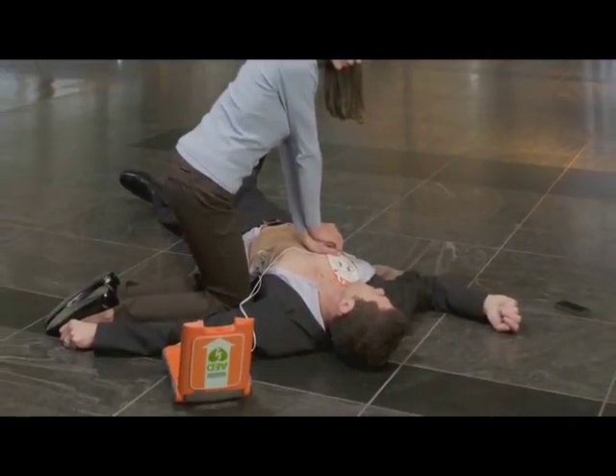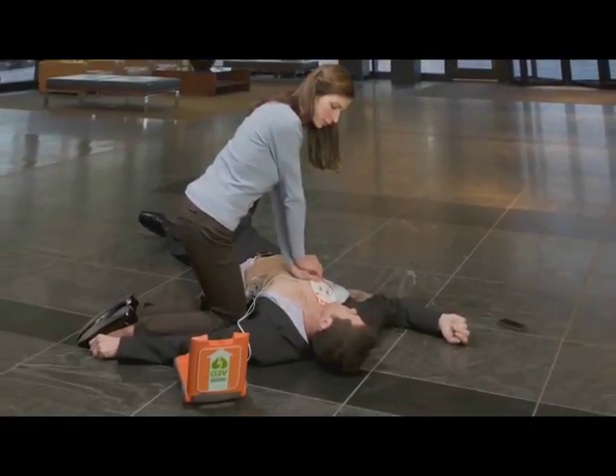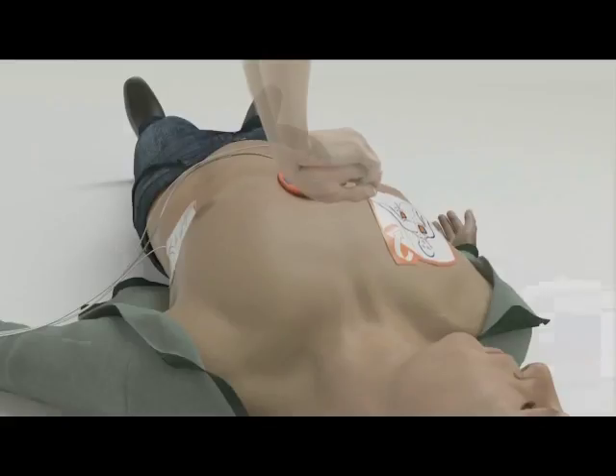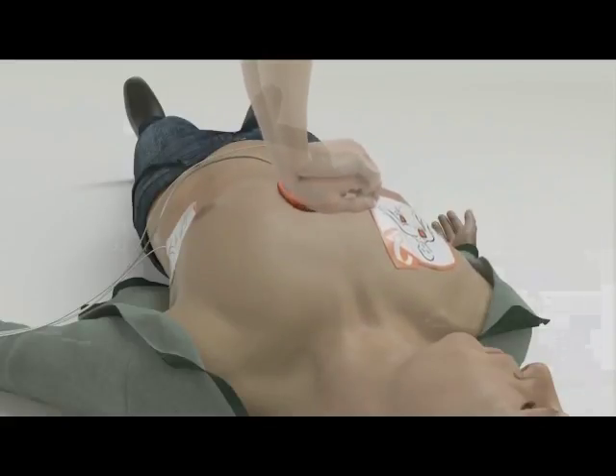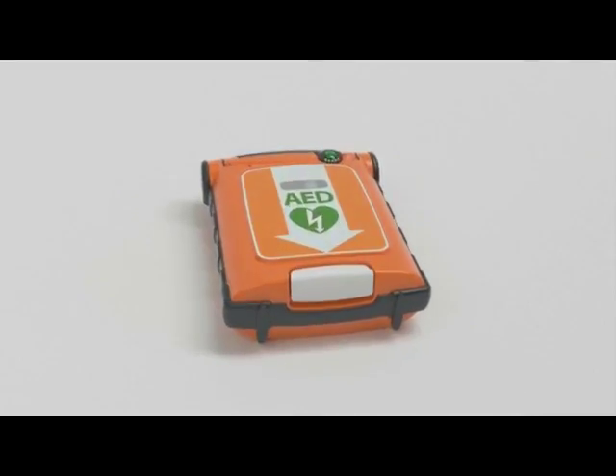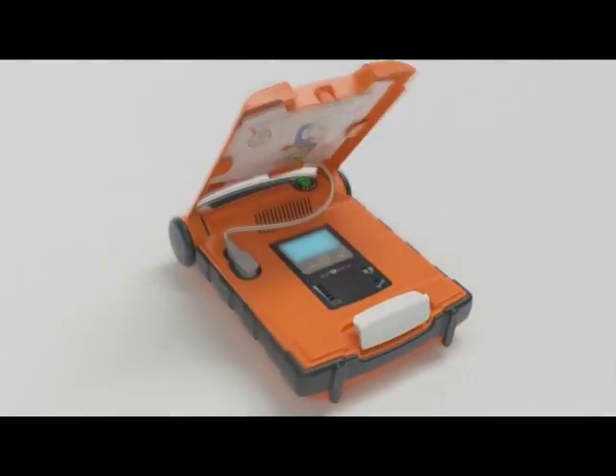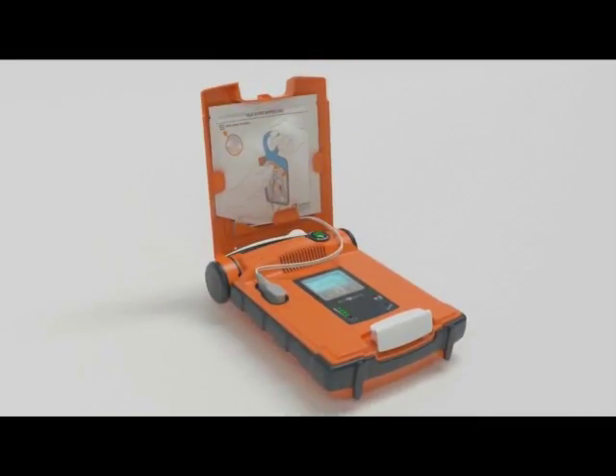The G5 will give you feedback on how effectively you are performing CPR. The G5 will advise if you are doing your compressions correctly — either too fast or too slow, too deep or not deep enough. If there is no green package in the lid with a CPR device and only standard electrode pads are connected, the AED will still guide you through how to perform CPR along with the metronome for 30 compressions as well as the two breaths. The only difference is that the AED will not give you feedback during CPR.